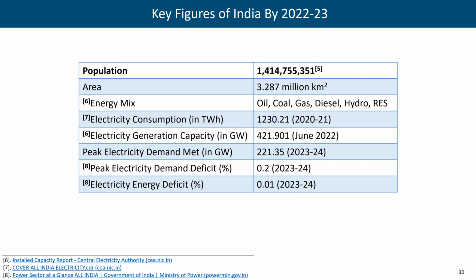So out of this 421, as we will see, around 47% is renewable. And whatever generation is there from renewable, we inject it into the grid. If at a particular instant, suppose solar was scheduled to generate 100 megawatt, but actual generation was not 100 megawatt, there can be several reasons. Solar irradiance was less, temperature was high, so output of solar could have been less. Wind, these things are not under our control.